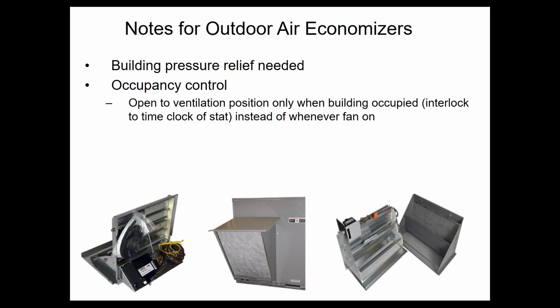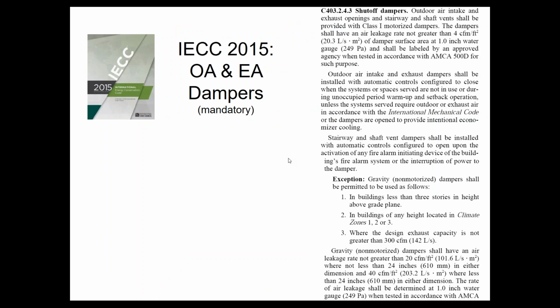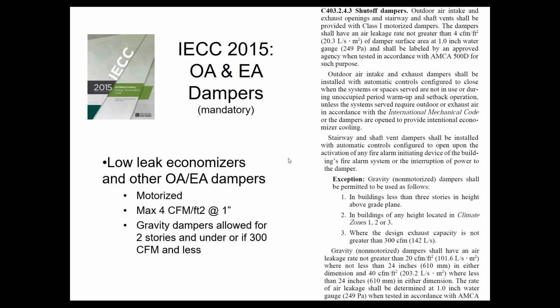When the building's unoccupied, you need to shut the outside air damper. Now you can open it for economizer mode for free cooling if you want to, but you do not open it for ventilation mode. We'll talk more about that in 2 weeks as well. All outside air intakes and exhausts from the building will need to have a low leak damper on them, a motorized low leak damper. There's an exception to that. If the building is under 2 stories or the CFM is really low, you can use a gravity damper instead of a motorized low leak damper.